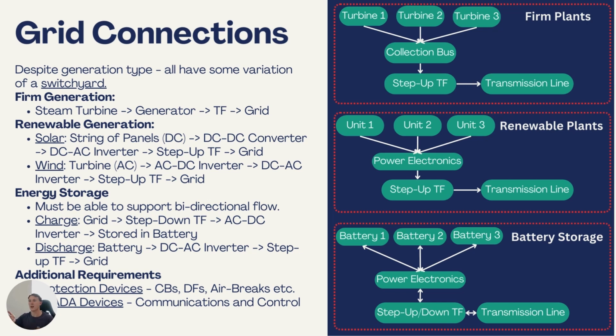What I've done is divided it into the 3 different generation types and the stereotypical layout for each. Let's start with firm generation. How these work is that the turbines get collated into what I've called a collection bus, which, because they have AC outputs, can then be put straight into a step-up transformer, which steps the operating voltage up to that of the transmission line connection, which can then be exported to the grid.